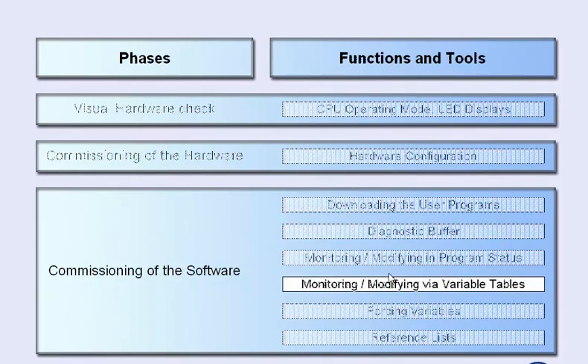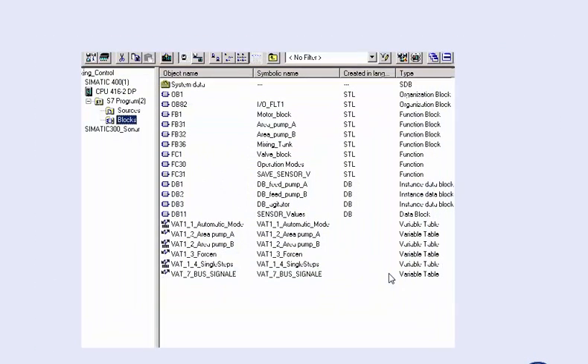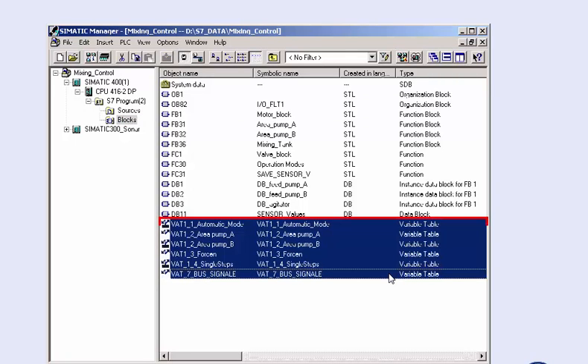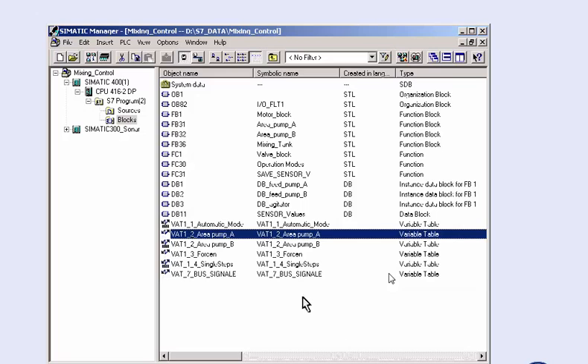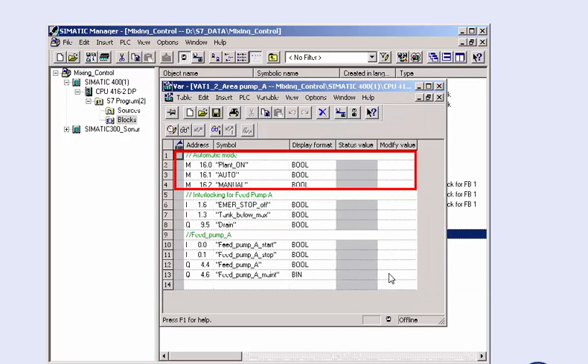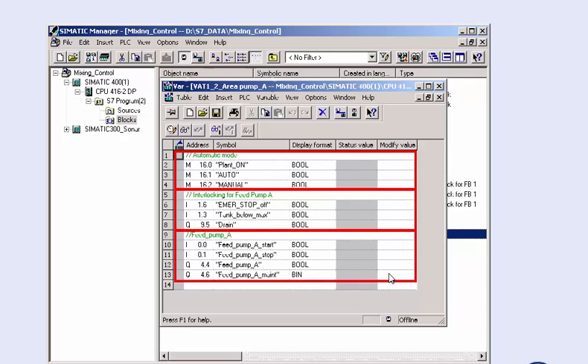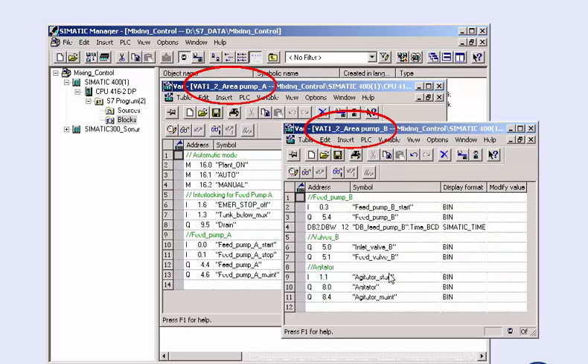Using the global variable table, you can now also perform this on any other block and this way control the entire user program. An elegant method of preparing several test scenarios is the individual generation of different variable tables. These tables can be generated in the implementation phase and saved in the offline project. You have the option of commissioning individual machines, plant components or also compiling individual variables for certain commissioning sections. This enables you to fix planned test processes in a reproducible manner.